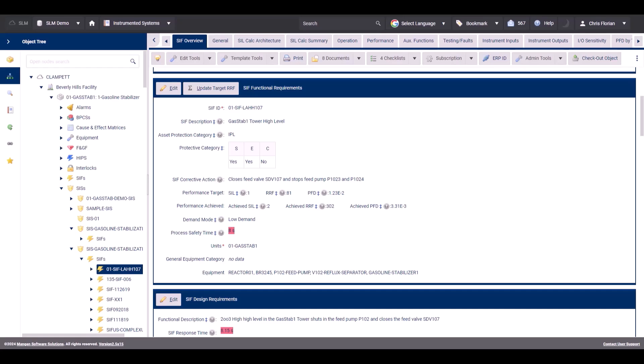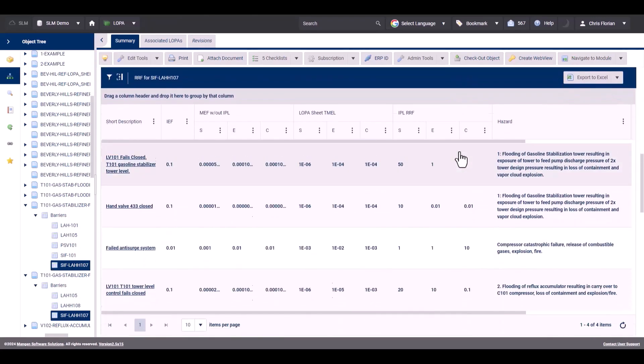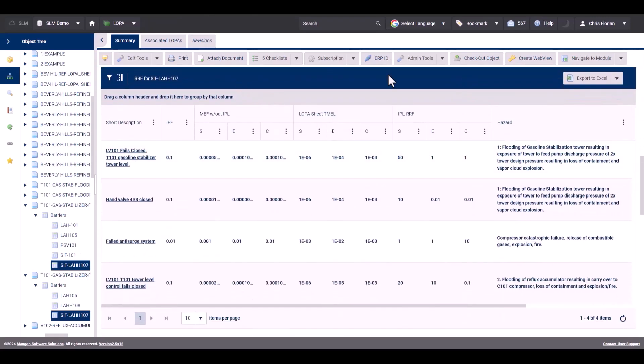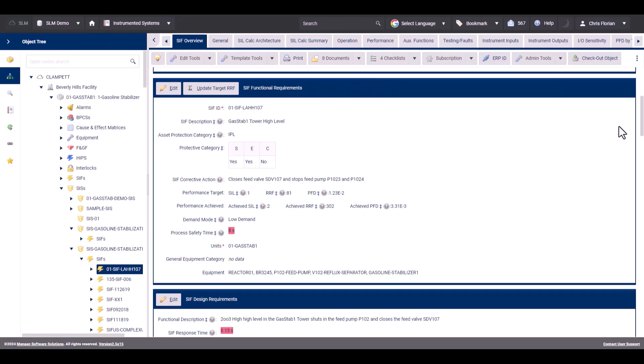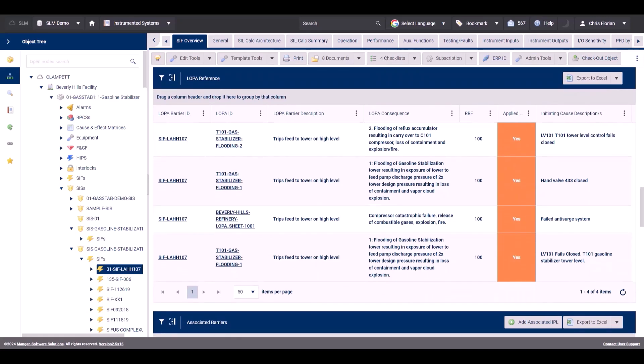The second group of information shared between LOPA and Instrumented Systems is the PHA scenario information. We can see this information on the barrier or IPL tab, by scrolling down to the risk reduction factor for the SIF. This table displays the scenario information, including initiating cause for the short description, the risk reduction factor for each of the scenarios, and the hazard or consequence.